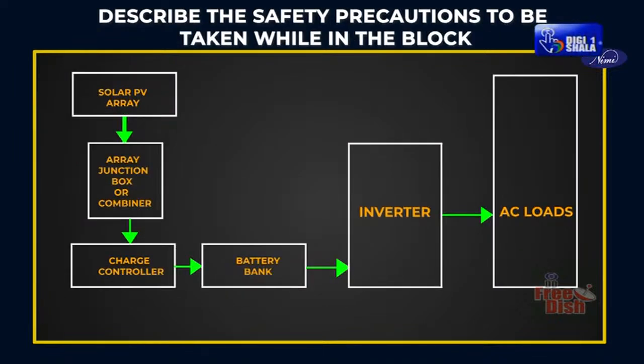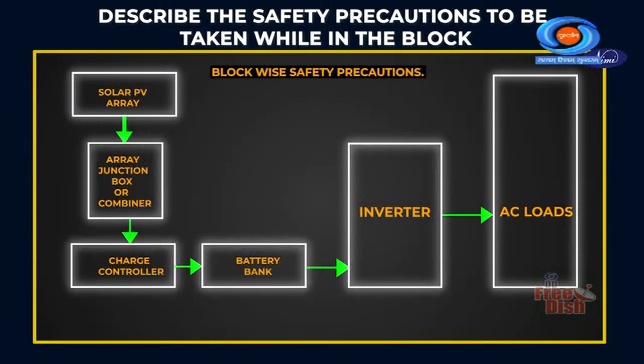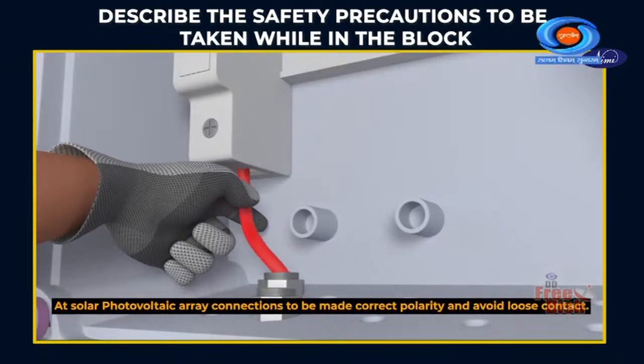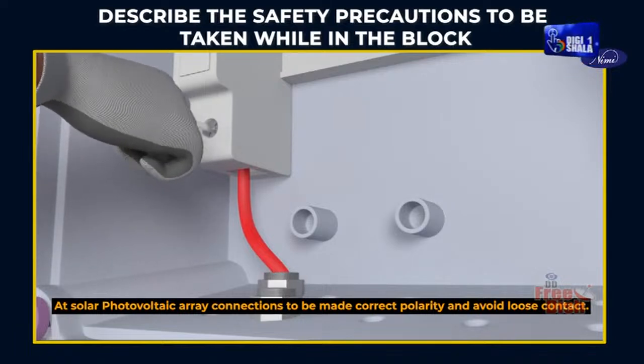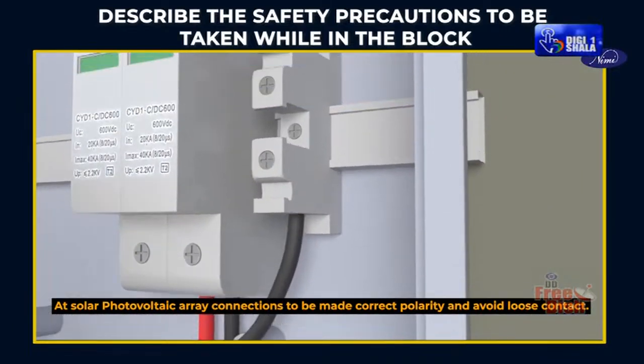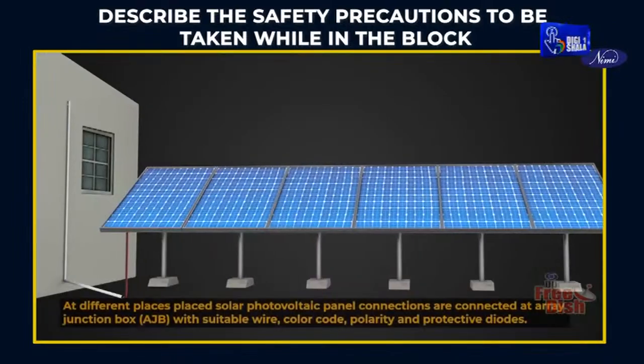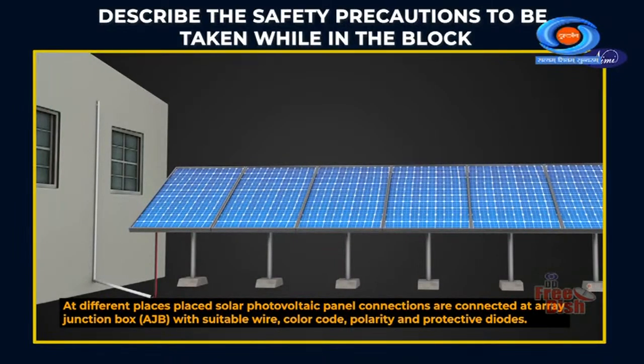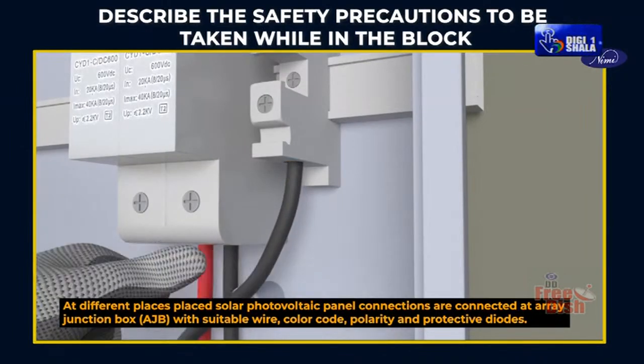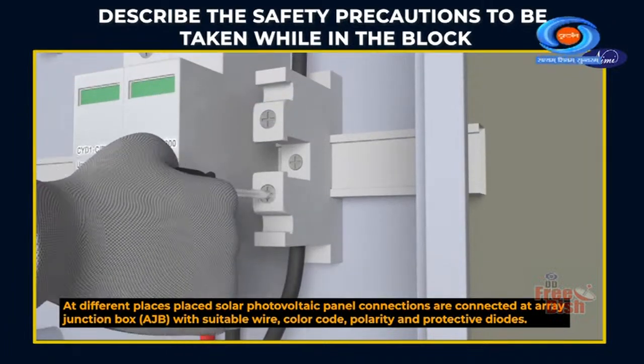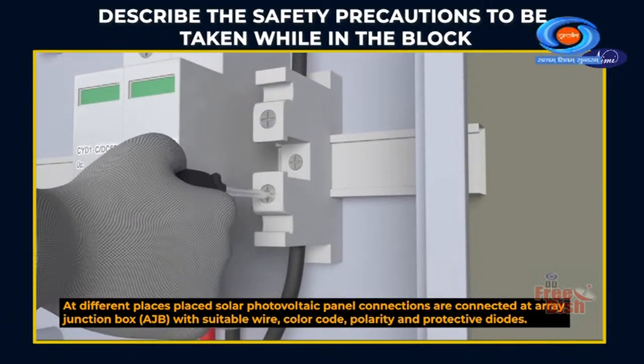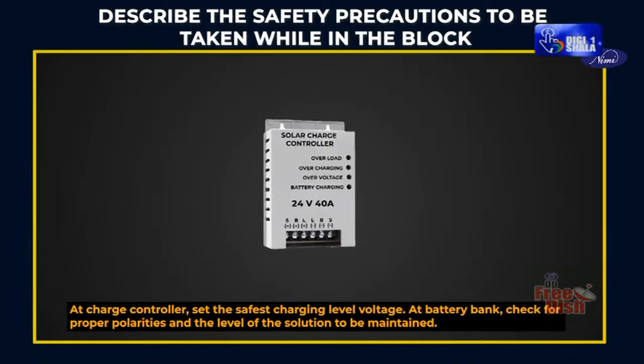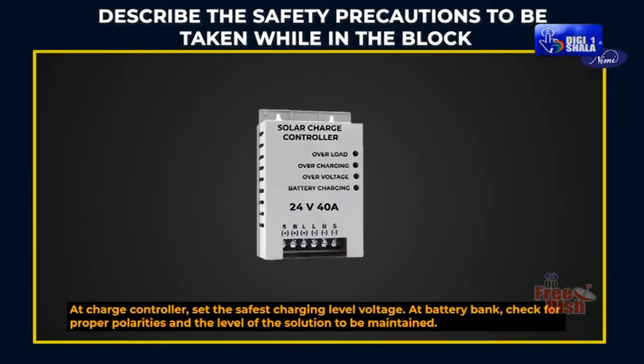Describe the safety precautions to be taken while in the block. Block-wise safety precautions. At solar photovoltaic array, connections to be made with correct polarity and avoid loose contact. At different places placed solar photovoltaic panel, connections are connected at array junction box with suitable wire, color code, polarity and protective diodes. At charge controller, set the safest charging level voltage.